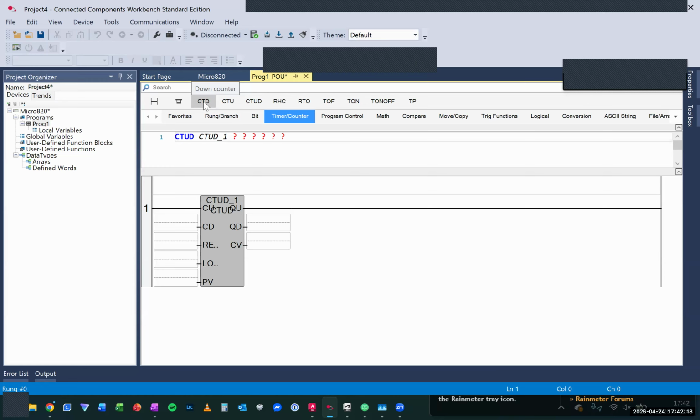That's an example. Once again, we need to put a trigger. What is the thing that's triggering? Now there are 2 types of triggers. That's what I was saying earlier. There's the trigger for when you're adding, so that's count up. You see that CU? And then there's the count down trigger. Both of those are going to constantly be undoing each other. And the count value, CV, is going to show the total number from those 2 results.